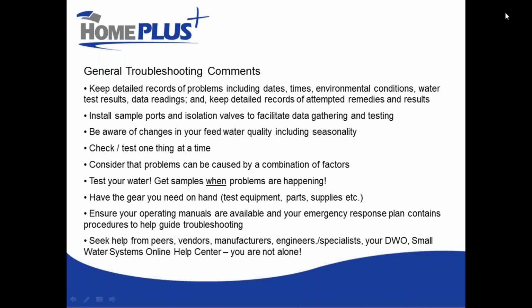Test, and test more if you have the ability to do it. And specifically, make sure you get water samples while the problem is occurring. Quite commonly in water treatment plants you get intermittent problems, intermittent poor water quality, intermittent alarms, that sort of thing. And you grab a sample the next day and the problem's gone. So we look at the water test result and everything looks normal. We want to try and grab a sample right during that problem event, and potentially from multiple different sample ports within the system. It really goes a long way to identifying intermittent issues.